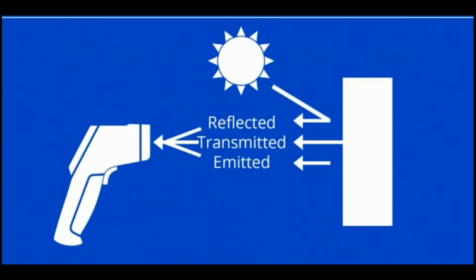The IR thermometer then works by focusing the light that is coming from that object in the form of infrared rays and tunneling that light into a detector known as a thermopile. This thermopile turns the IR radiation into heat.